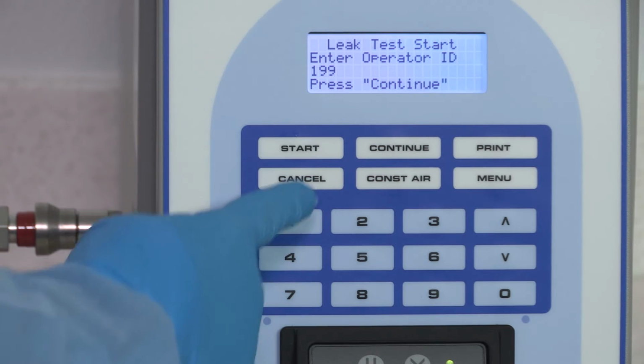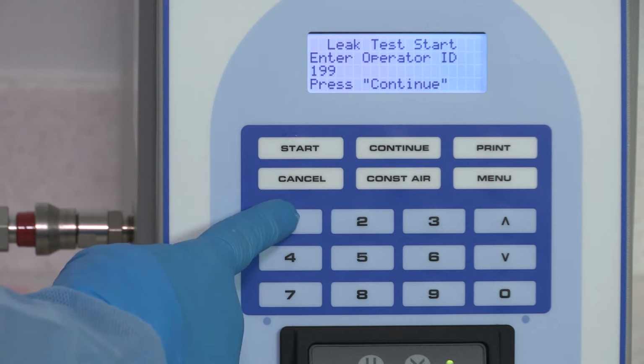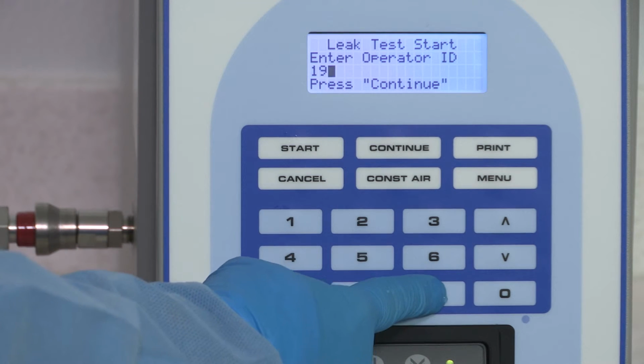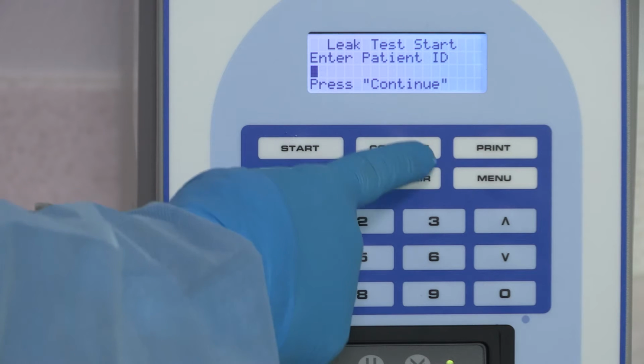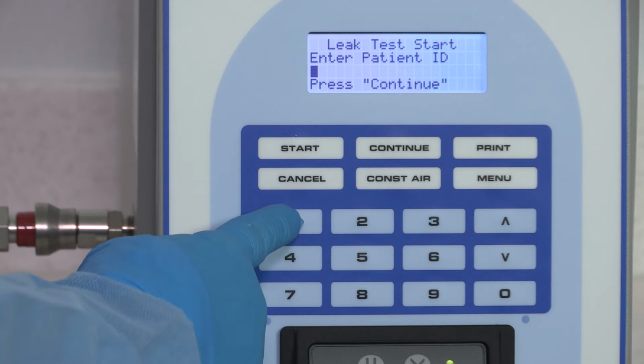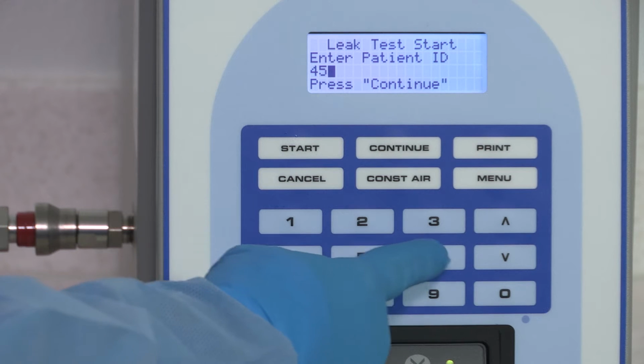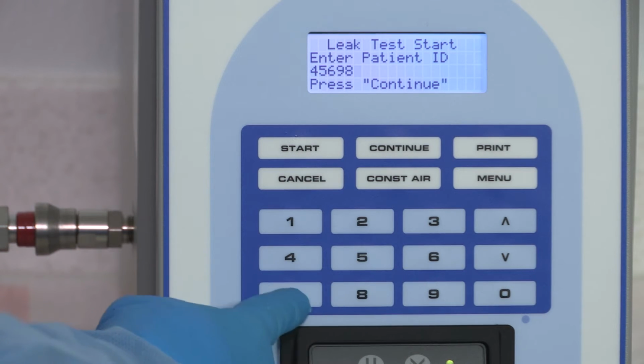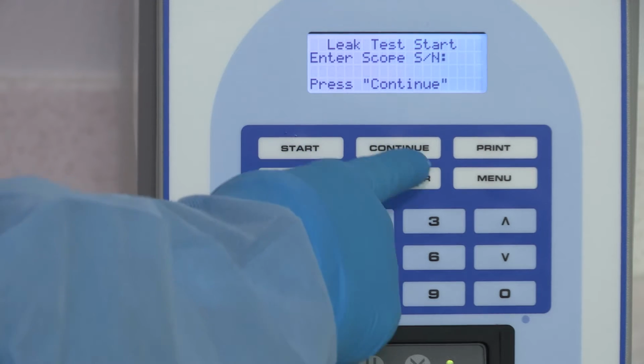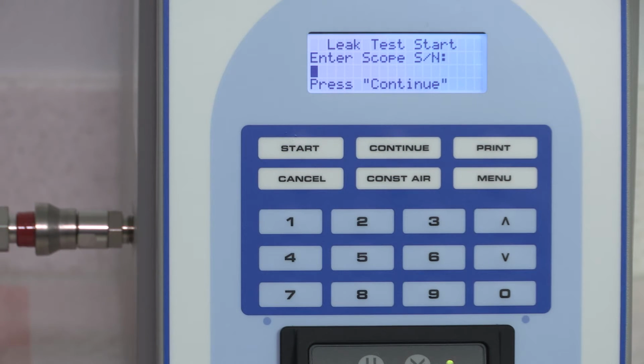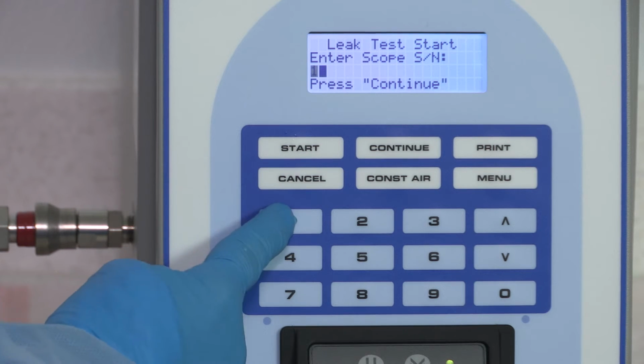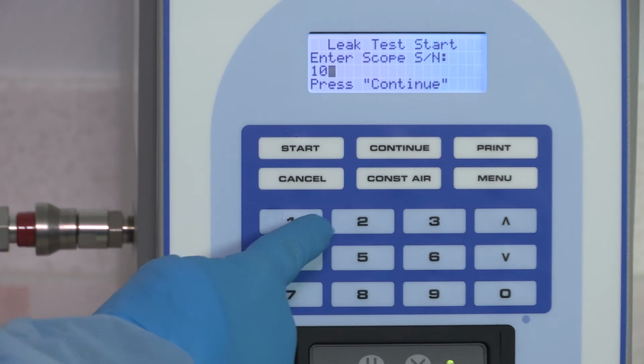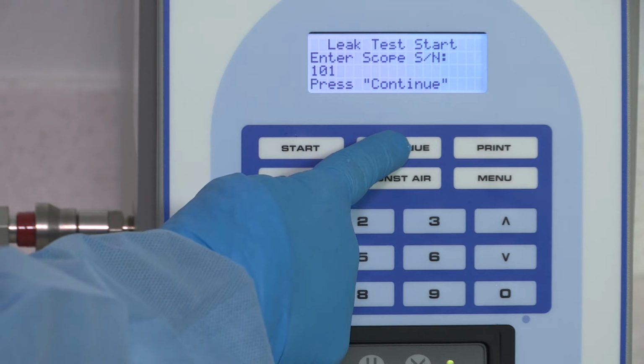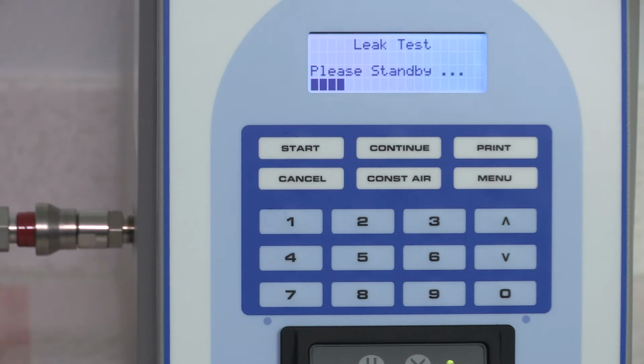If the optional operator ID prompt is activated, use the numeric touchpad to enter your operator ID number. A maximum of 4 digits is allowed. Then press Continue. If the optional patient ID prompt is activated, use the touchpad to enter the patient ID number. A maximum of 10 digits can be entered. Then press Continue. When the Enter Scope serial number prompt displays, enter the endoscope's ID or serial number using the numeric touchpad, and then press Continue. A maximum of 10 digits can be entered. If there is a duplicate serial number within your endoscope inventory, use a unique number for the endoscope to ensure complete traceability.